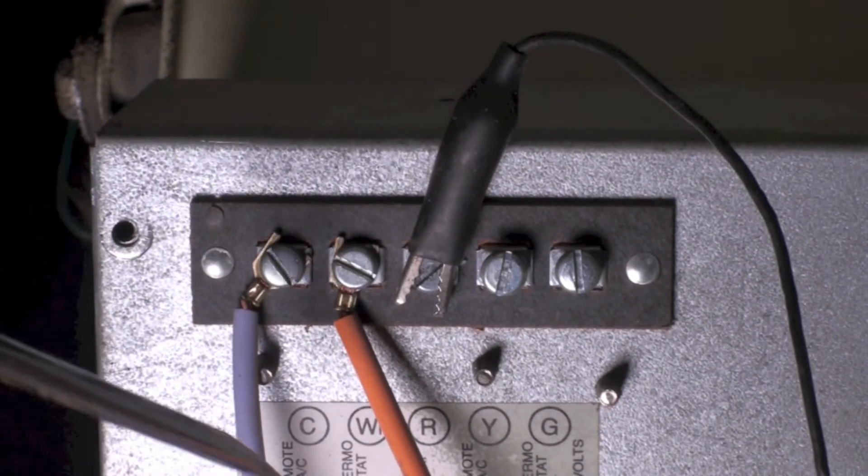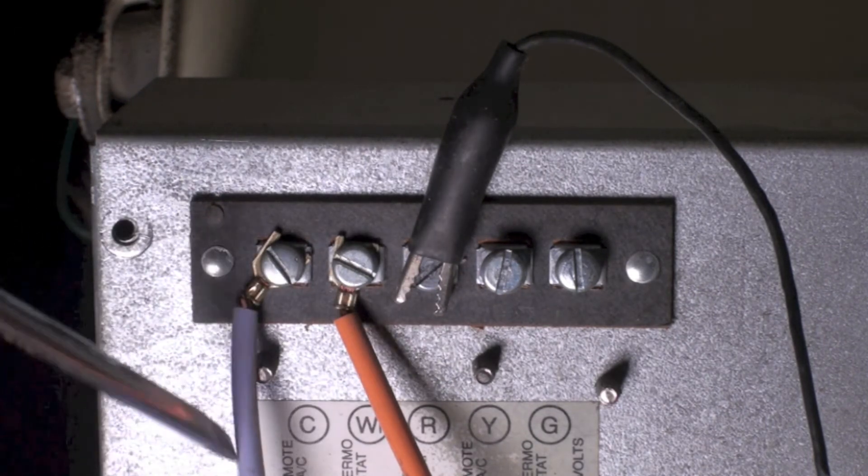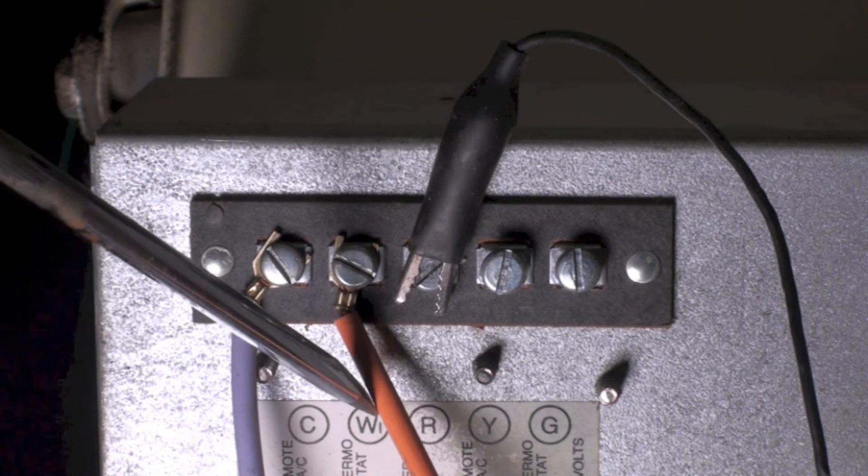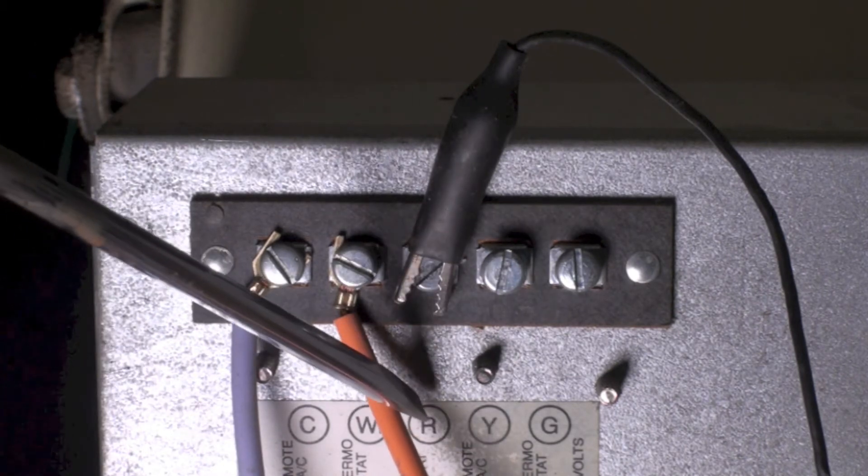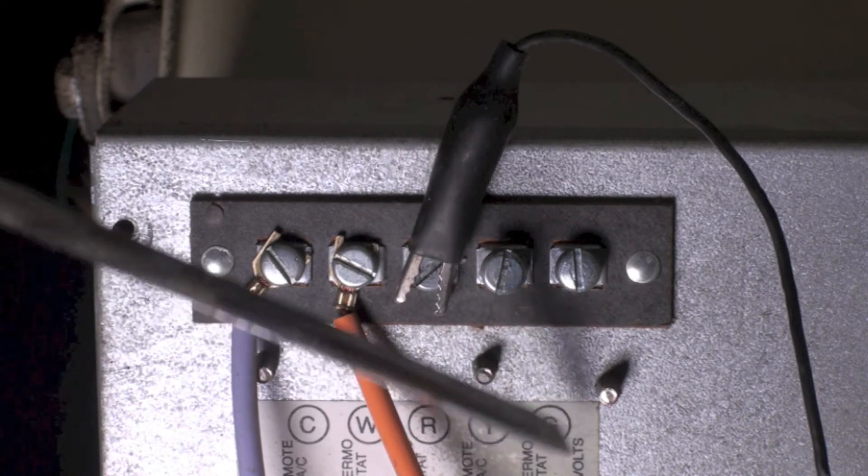You can see we have C, which is common from the transformer - this is all 24 volts down here. Next one over is W, which is the heat; R, which is the other side of the transformer, the switch side; and Y and G.